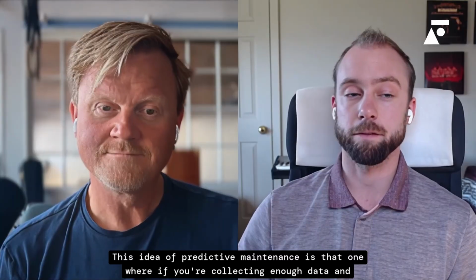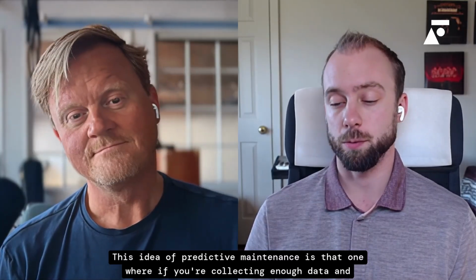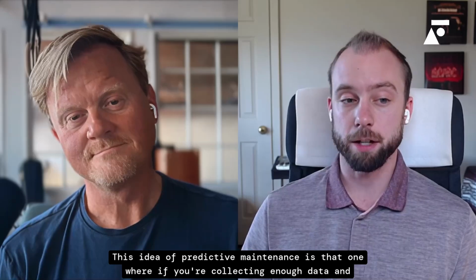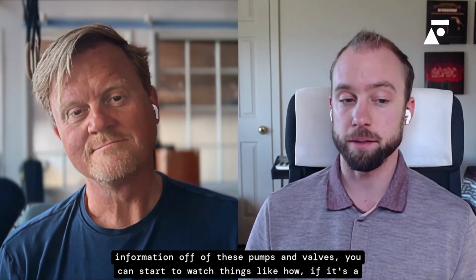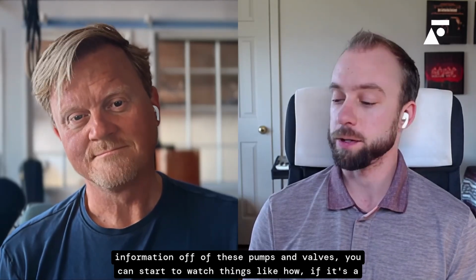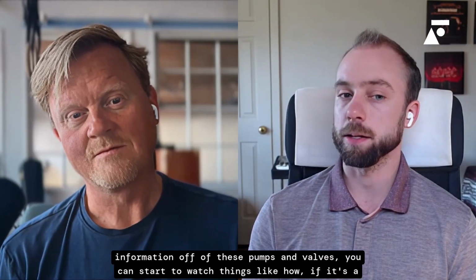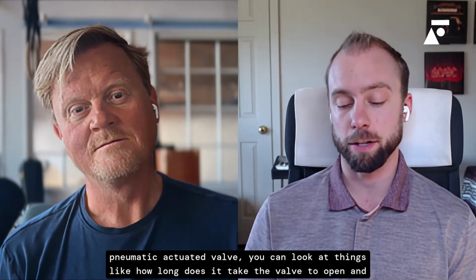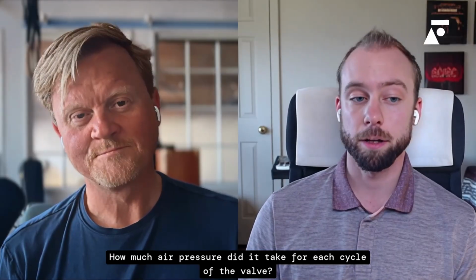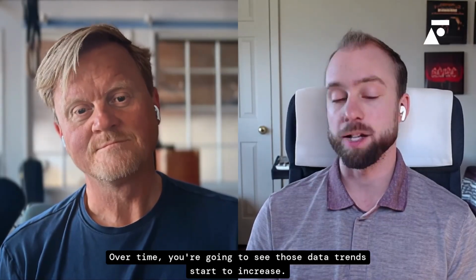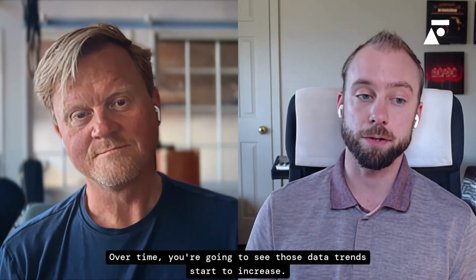This idea of predictive maintenance is that if you're collecting enough data off of these pumps and valves, you could start to watch things like, if it's a pneumatic actuated valve, how long does it take the valve to open and close? How much air pressure did it take for each cycle of the valve? Over time, you're going to see those data trends start to increase.